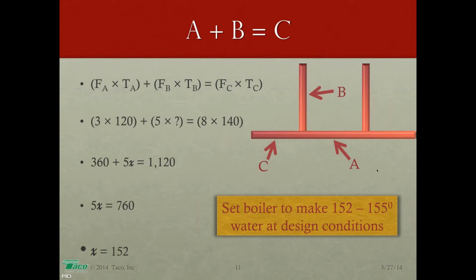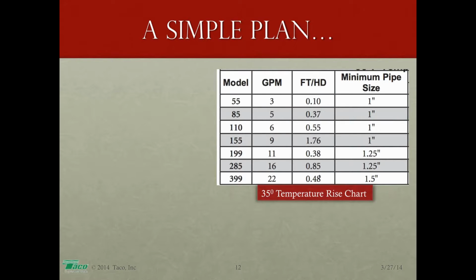There is an easier way to do it, provided that the manufacturer gives you the information that you need in the manual. All right? This is a manual from Lochinvar, and what you do is check the manual and look up the model boiler that you're going to be installing. Let's say it's the Model 85, and then you look at the different charts and find the temperature rise that you're targeting. What's the temperature rise, the delta T across the boiler, that you're targeting? Again, they'll give you charts for 20, 25, 30, 35. Here we're using the 35 degree temperature rise chart.